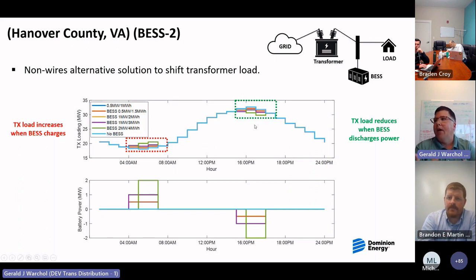The bigger battery I put there, I can essentially take all the load off the transformer if I had the real estate to do it. But this is why we call it a non-wires alternative solution - because of the way the power system is planned, we expand the system based on load growth, right? So as factories come online and we get more load out of our substations, this transformer eventually gets to the point that I either have to split out the transformer, put in a second one, or split out circuits.